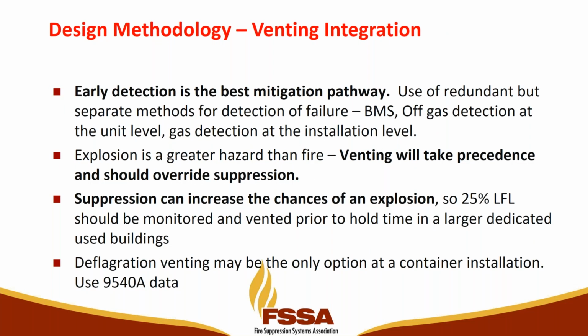I would very strongly favor, at first, mitigation and early detection. Redundant to failure to the BMS, off-gas is a very early warning and can help you. It may not stop it, depending upon what the failure mode is, but it's obviously something that can help mitigate. Explosion can be a greater hazard than the fire, so you may find yourself in a position that venting has to take precedence over and should override suppression. So if you release the system, but you're still seeing high levels of gases, you may have to start venting. So it needs to be monitored as part of your complete system to understand, are my gas levels still rising?